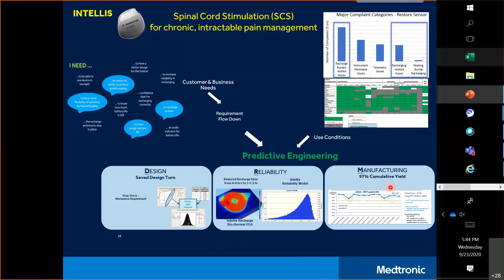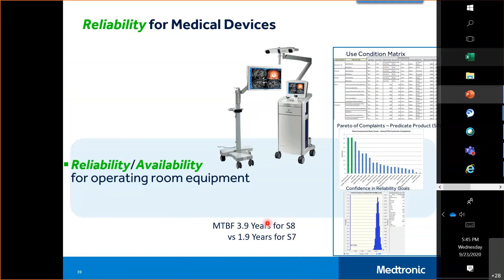Here's another. This is a medical device that's used in an operating room called Stealth Station S8. Again, showing the reliability side and availability side. One of our people built a use condition matrix to look at those noise factors that affect reliability. We also did a Pareto of complaints from the predicate product, Stealth Station S7. That earlier product, this is Stealth Station S8. And then he built a reliability model and optimized the reliability for Stealth Station S8. And he was able to get the mean time between failures from 1.9 years on the earlier product, more than doubling it to greater than 3.9 years for Stealth Station S8.